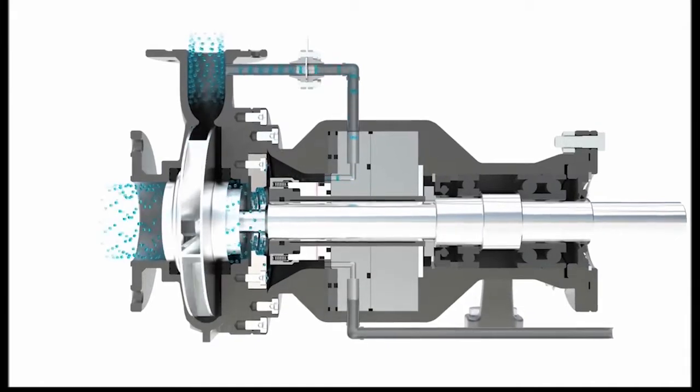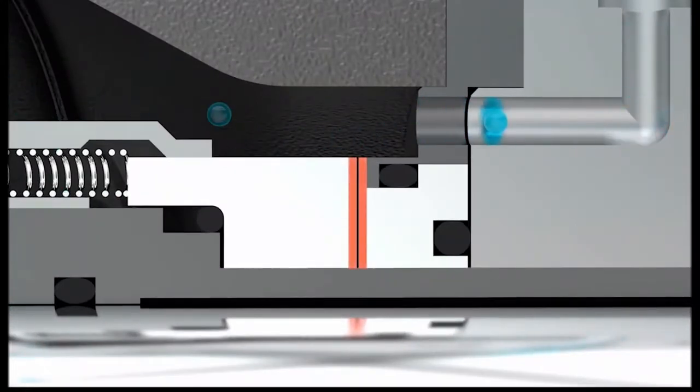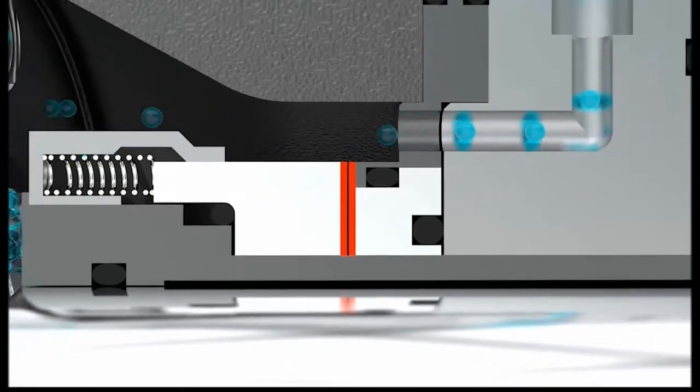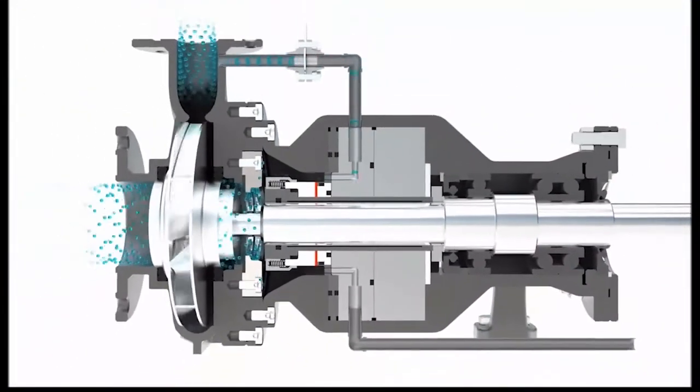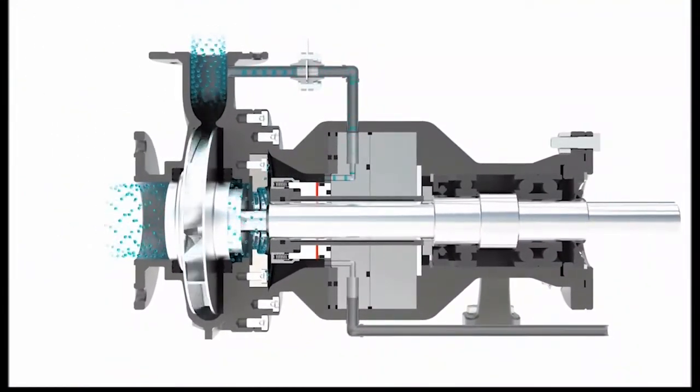This occurs when flow varies due to pressure fluctuations in the stuffing box, as it would with an orifice plate or needle valve. On the other hand, flush fluid is wasted when too much flow is provided.